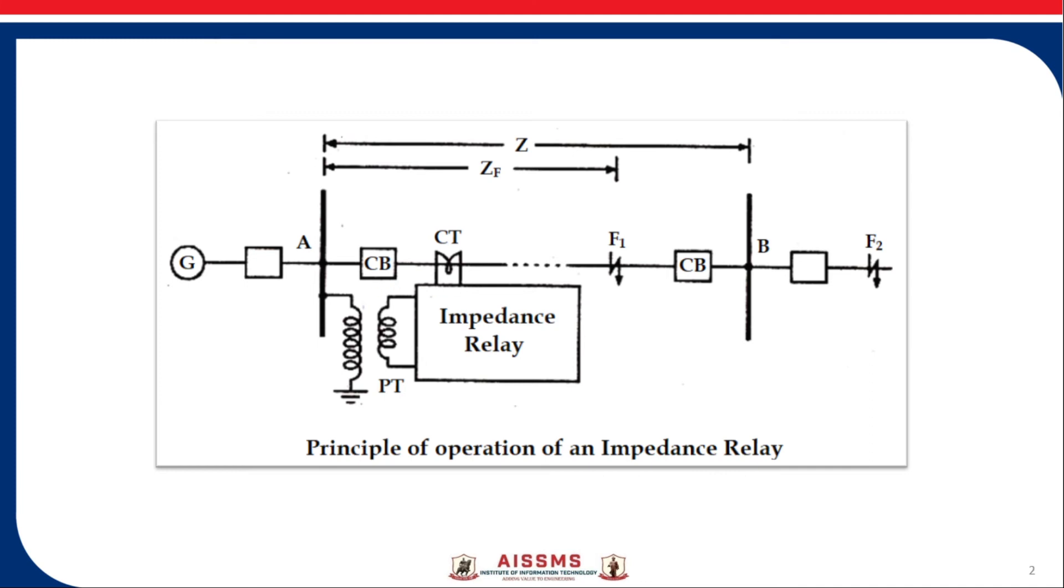This figure shows the basic principle of operation of impedance relay. The voltage element of the relay is excited through potential transformer PT from the line to be protected. The current element of the relay is excited from CT in series with the line. The portion AB of the line is protected zone.